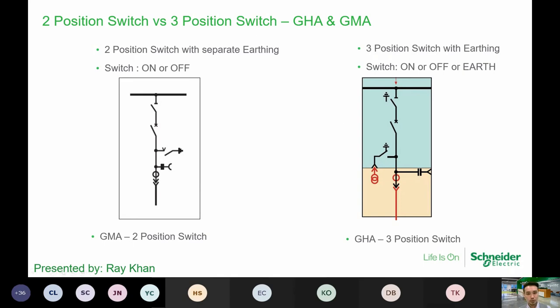The three position switch operates on the on, off, and earth concept, whereas the two position switch works on the on, off. The earthing is done through a separate spring loaded earthing switch, which is also achieved through the mechanical interlock itself. Generally, step one is that the circuit breaker is opened. Then the isolator is opened. And once the isolator is opened, the earthing switch will be switched on, and then it is connected to earth.